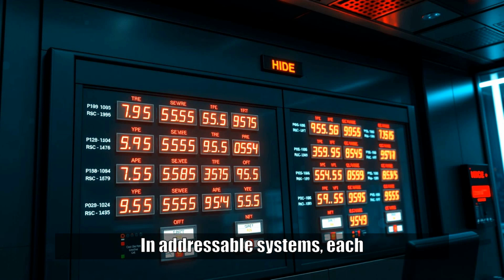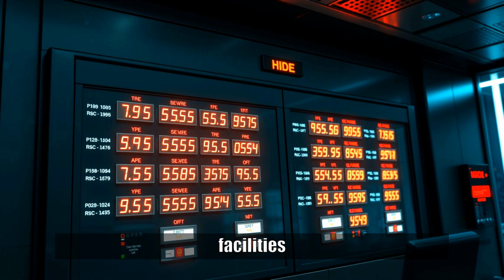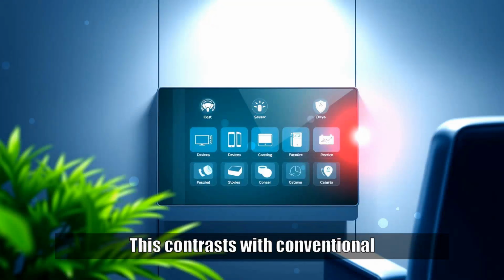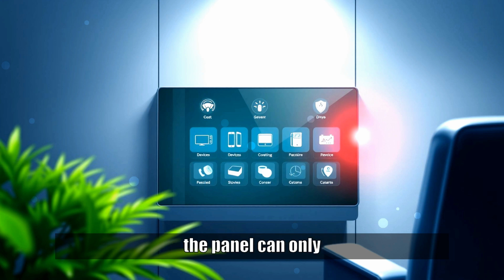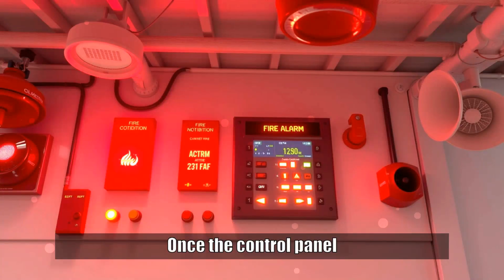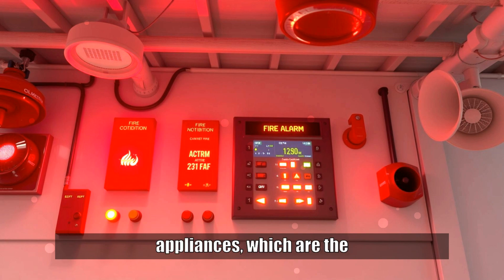In addressable systems, each device has a unique digital address, allowing the panel to pinpoint the exact location of the alarm, a crucial feature in large buildings or high-risk facilities. This contrasts with conventional systems, where devices are grouped into zones and the panel can only identify the affected zone, not the specific device.